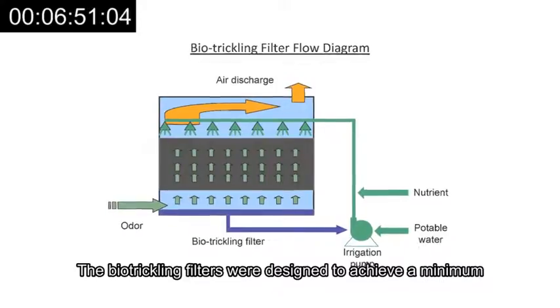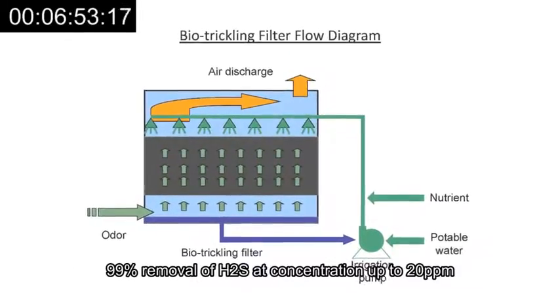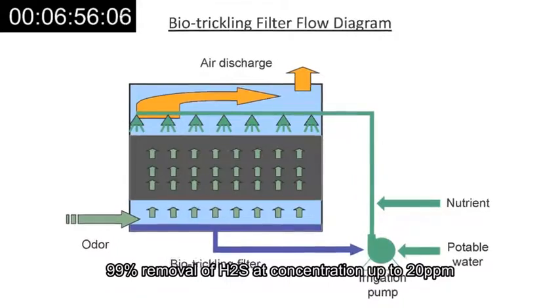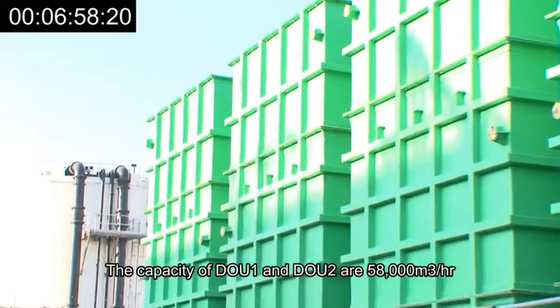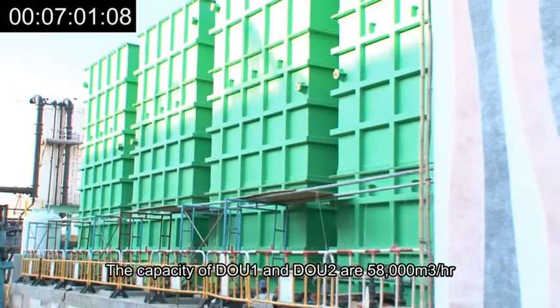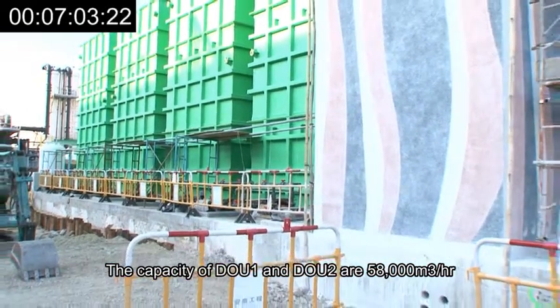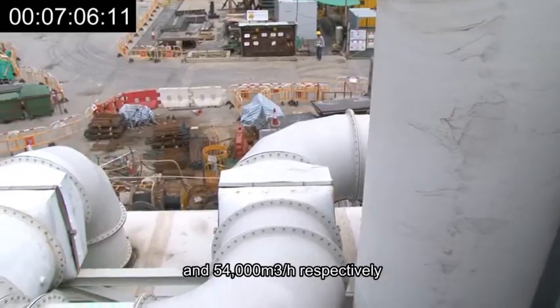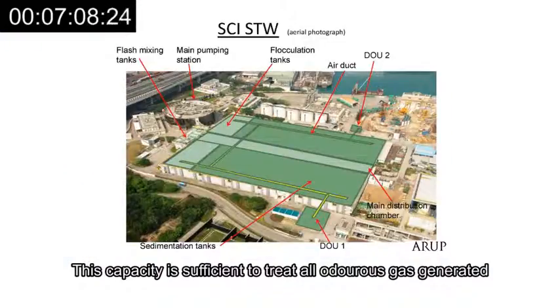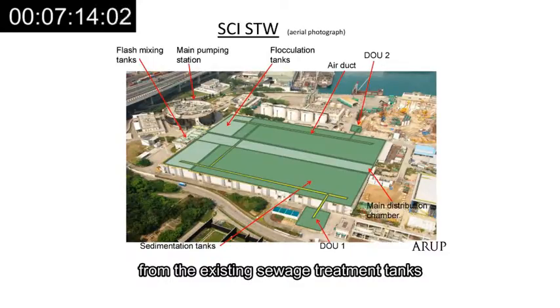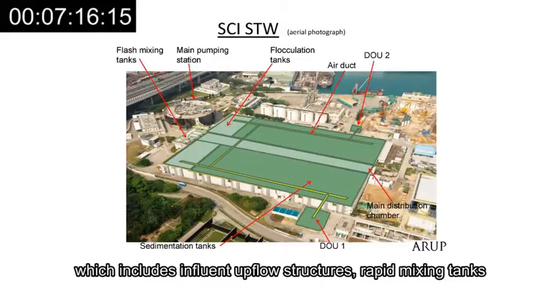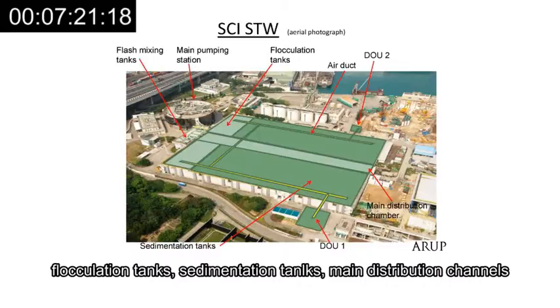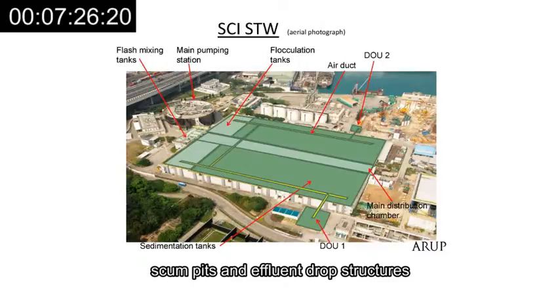The biotrickling filters were designed to achieve a minimum 99% removal of H2S at concentrations up to 20 ppm. The capacity of DOU1 and DOU2 are 58,000 m3 per hour and 54,000 m3 per hour, respectively. This capacity is sufficient to treat all odorous gas generated from the existing sewage treatment tanks, including influent upflow structures, rapid mixing tanks, flocculation tanks, sedimentation tanks, main distribution channels, scum pits and effluent drop structures.